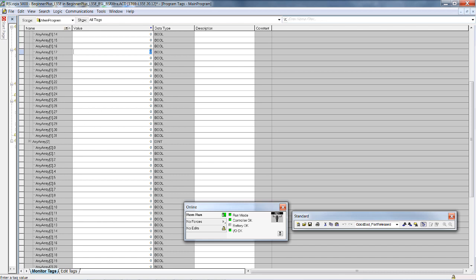Now we're doing this so you can watch these bits. What is critical to this demonstration is you being able to view the last few bits of 1, which would be these right here, 27, 28, 29, 30, and 31, and the first 5 bits of 2: 0, 1, 2, 3, 4. So you can see the shift. Don't forget that you have an output that energizes with an on state for the first bit and the unload bit, but you're going to ignore the other 2 outputs.